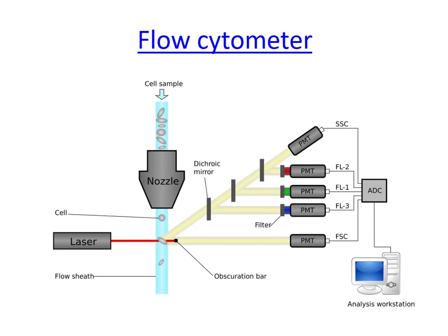So this is a flow cytometer. These are the basic components. And essentially you take, for instance, a blood sample, the machine itself takes up the blood, and here you can see the sample. It goes through a nozzle, and this nozzle enables the cells, a mixed population of cells, to actually flow in a single file.